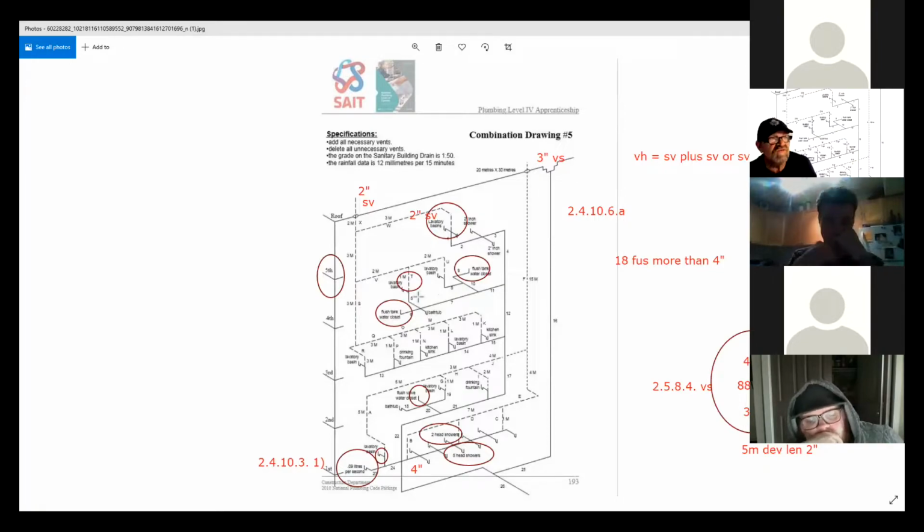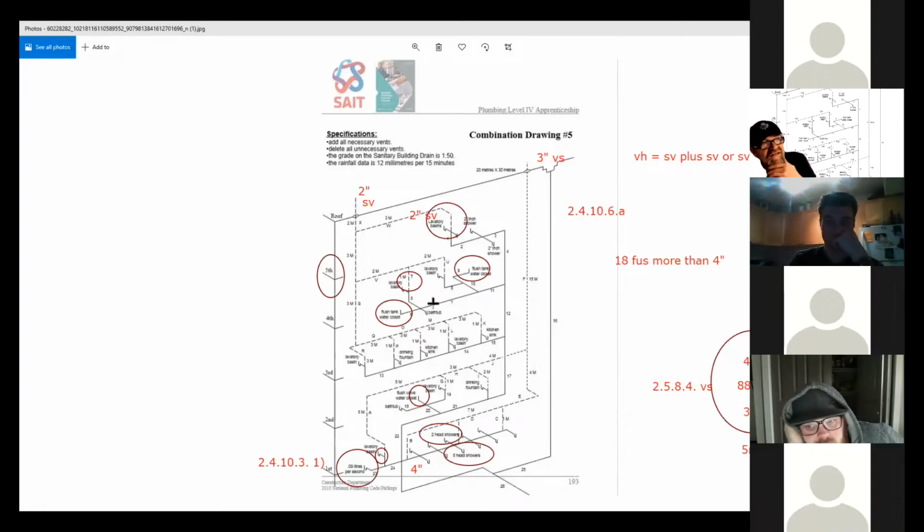these 3 fixtures, right? And notice here how, the only thing I don't like about these drawings is they don't show Ys and 45s. This Visio drawing is from BCIT originally, years ago. And notice how he's doing his wet vent? That's a symmetrical Y, it's not a cross T. It's supposed to be, and he ran straight to the toilet. Works perfect, right? Bathtub on this side, vanity on this side, wet vent here, continuous vent here. So that's a continuous vent.